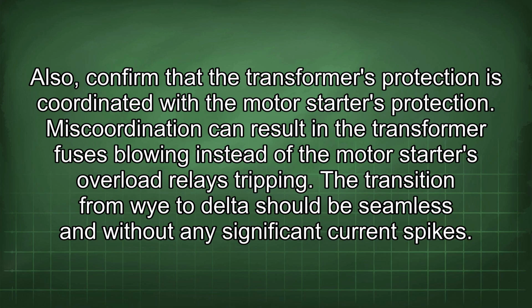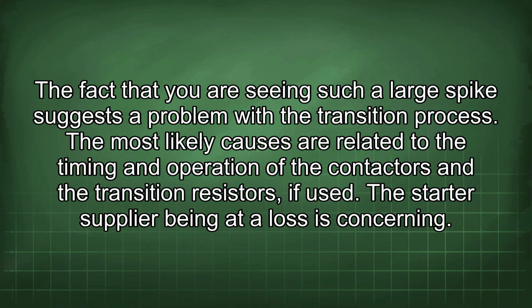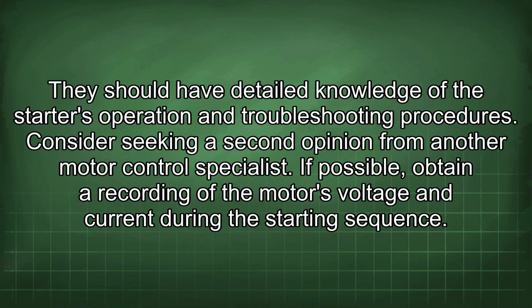The transition from Y to Delta should be seamless and without any significant current spikes. The fact that you are seeing such a large spike suggests a problem with the transition process. The most likely causes are related to the timing and operation of the contactors and the transition resistors if used. The starter supplier being at a loss is concerning. They should have detailed knowledge of the starter's operation and troubleshooting procedures. Consider seeking a second opinion from another motor control specialist.